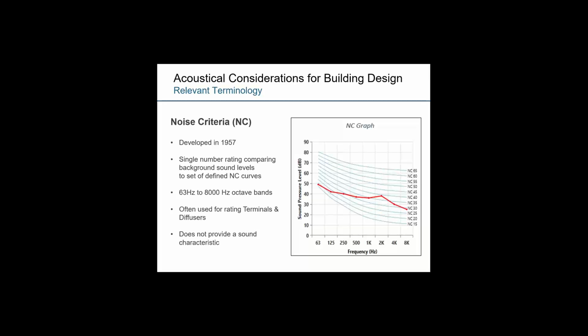NC was developed in the mid-1950s, and it's often used for referring to the background sound within a space, for rating products like terminals or diffusers, or even for diagnosing whether a space is acceptable or not. It is a little bit limiting in that all you really get is that single number reference, the NC value. You're not obtaining much information on the spectrum of sound, or whether there's a dominant frequency that's maybe causing that spectrum.